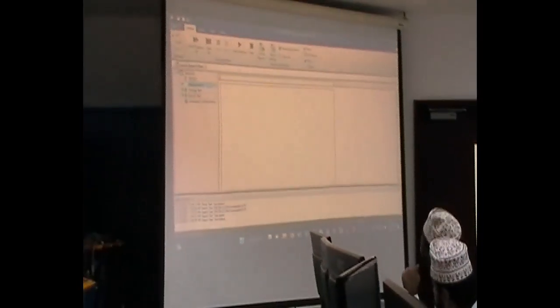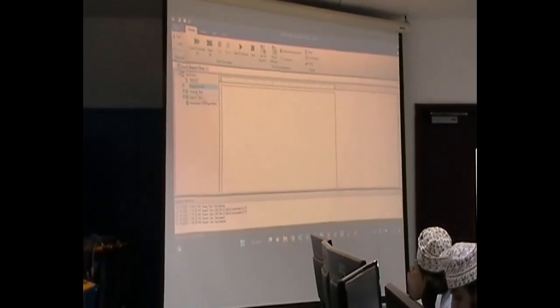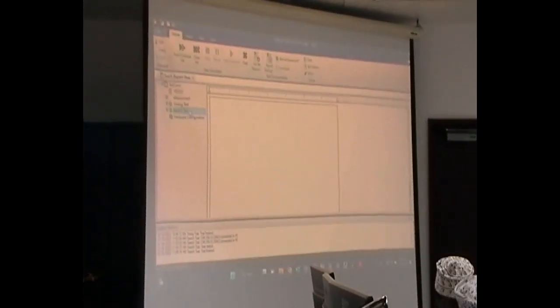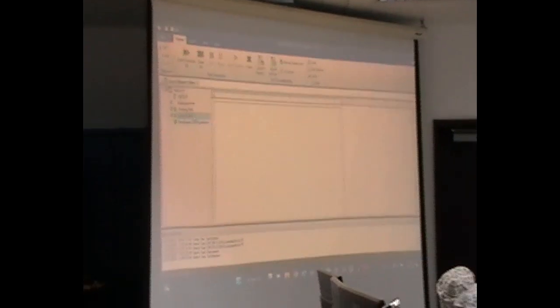Here I want to see the sensitivity of the setting only. Assuming I could have in the setting 20 ohm, but it operated in 19, or I have 25 ohm, it operates earlier, or later, if the impedance is larger. So, to summarize this, we've done the measurement test, the timing test to check the time, and the search test to check the reach of the relay. If you have any question, please.